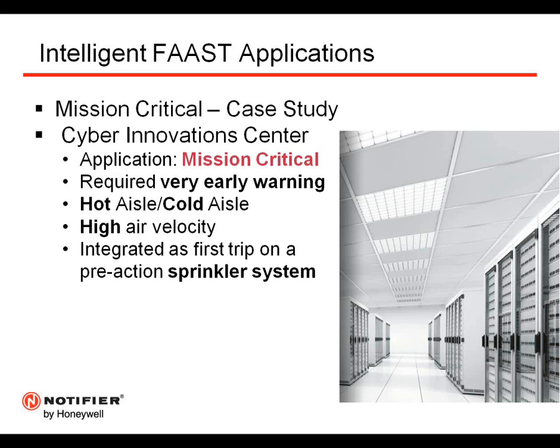And this is actually a hot aisle, cold aisle cooling strategy in this data center, which is something that's becoming more and more prevalent through data center applications. In this strategy, what they do is they cool the air surrounding the racks, and the servers actually pull that cool air through the rack into a hot aisle that's contained, so cooling themselves off and then exhausting the hot air up through the ceiling, which is then returned back to the CRAC unit.